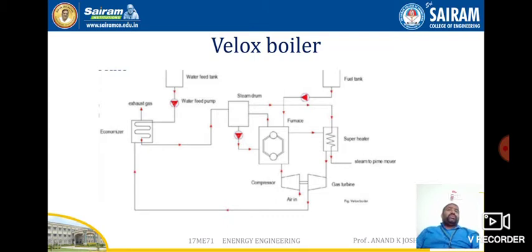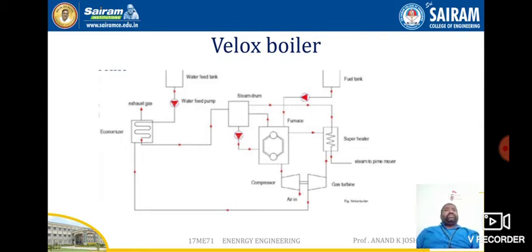The Velox boiler generates high pressure steam. The advantages include a very high combustion rate of up to 40 megajoules per cubic meter of combustion chamber volume. Low excess air is required as pressurized air is used, and the problem of draft is simplified. It is a very compact generating unit with higher flexibility, and it can start quickly even though the separator has a storage capacity of about 10 percent of the maximum hourly output.